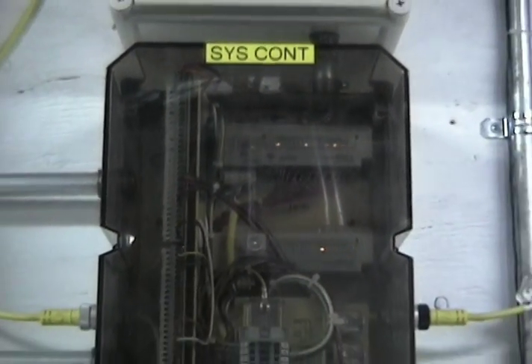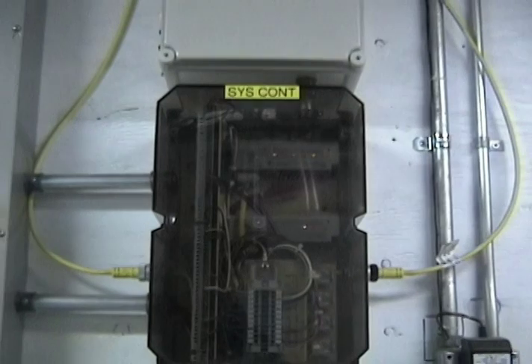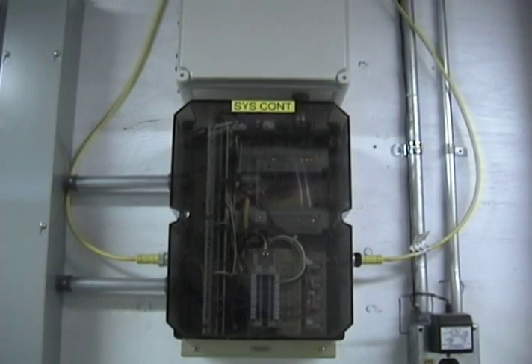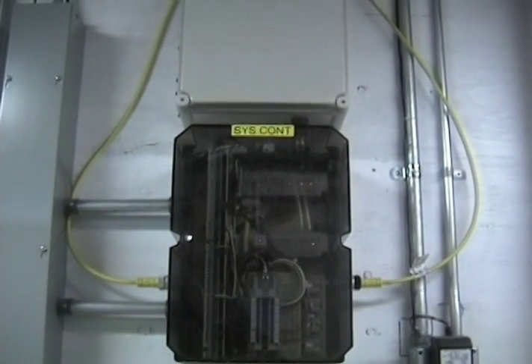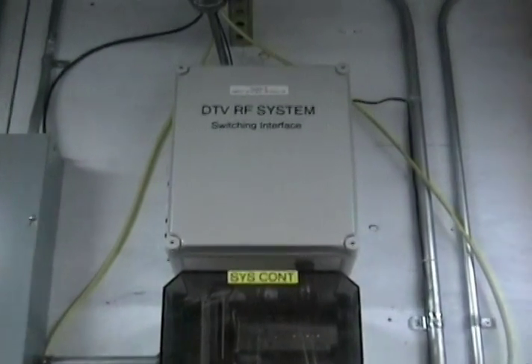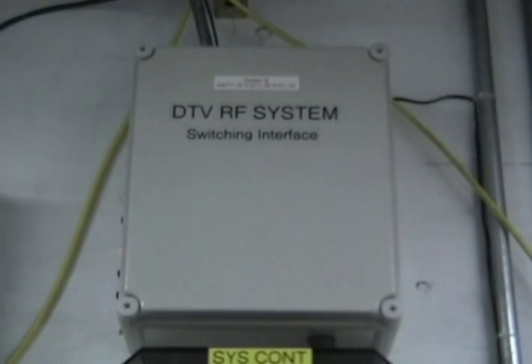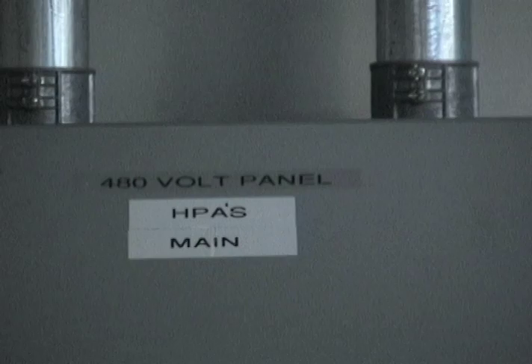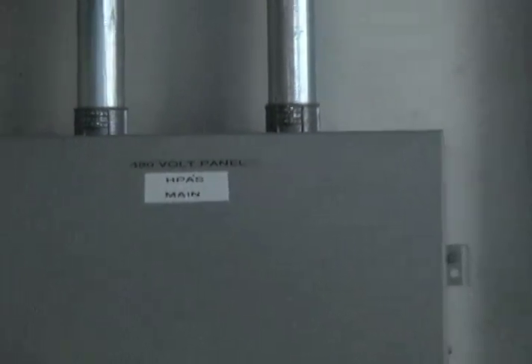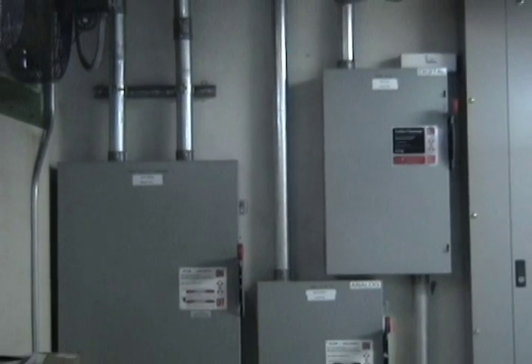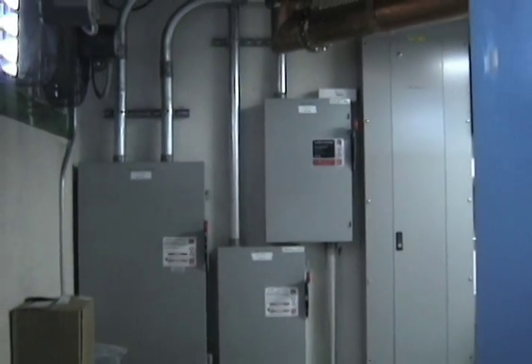All of the external systems are connected to this control unit, which in turn is connected to the transmitter. The unit above it is used to communicate with the combiner room's RF system on the roof. The 480-volt three-phase power that is used by the transmitter comes in through these fused disconnect switches.